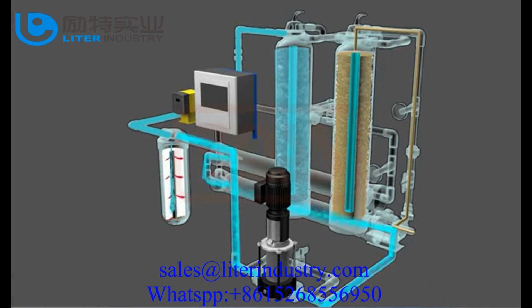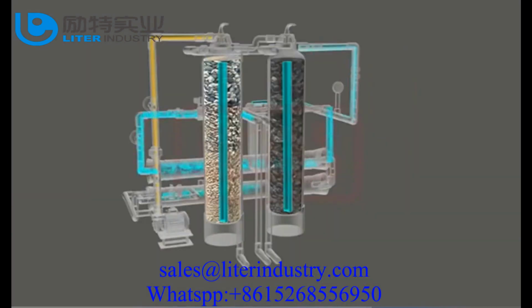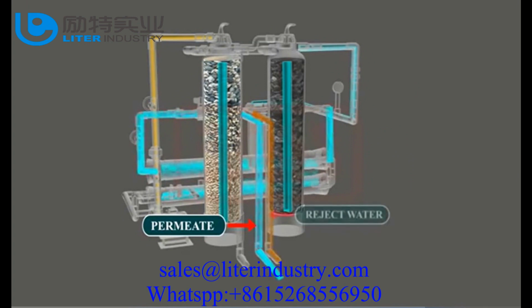Water then passes through the membranes, while most dissolved solids do not pass through the membrane. This pure water, which is achieved because of reverse osmosis, is also called permeate or product, which is used for various processes or can be stored in a storage tank to be used later. Part of the reject water is either recycled or can alternatively be reused.